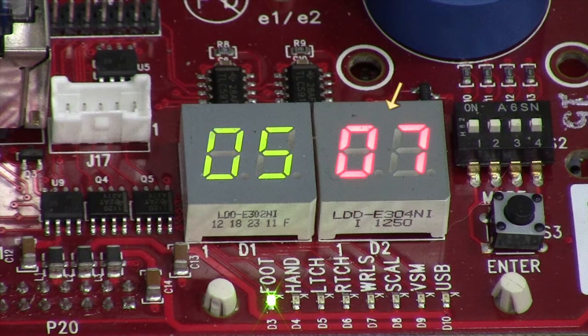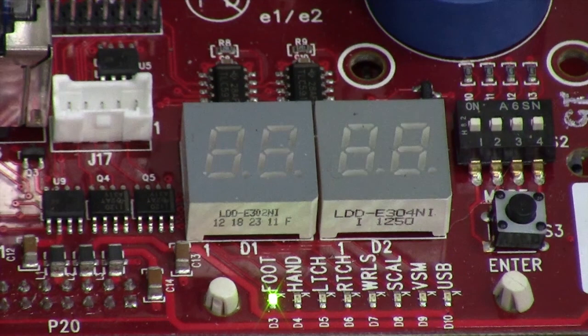The red display indicates what problem or symptom was detected. For example, 07 indicates that at least one foot smart sensor switch has been activated or is malfunctioning. If the problem or symptom is no longer present, the code will go away. The S2 switch and S3 switch on the machine control board are used to calibrate the table.